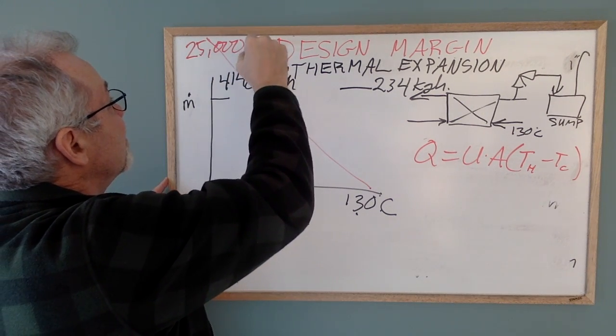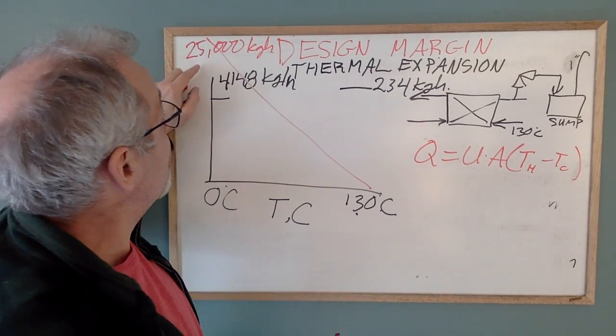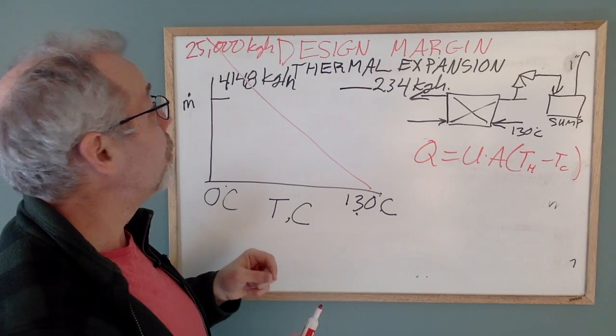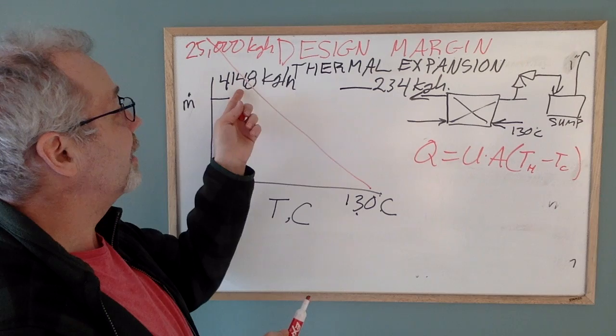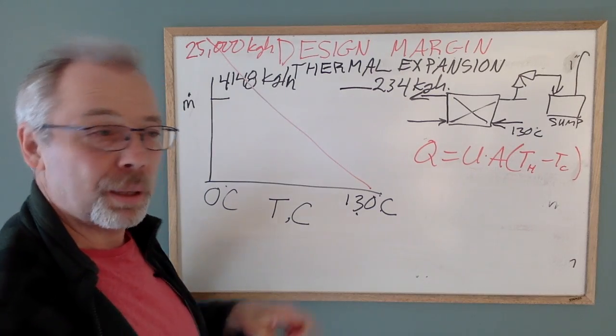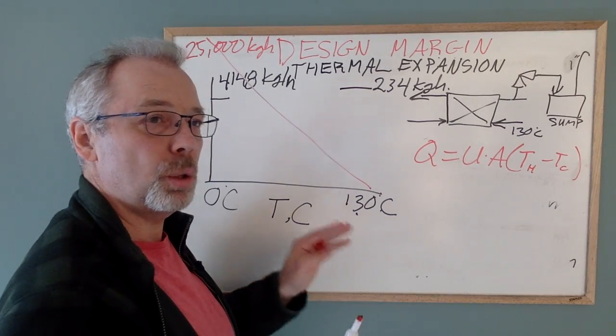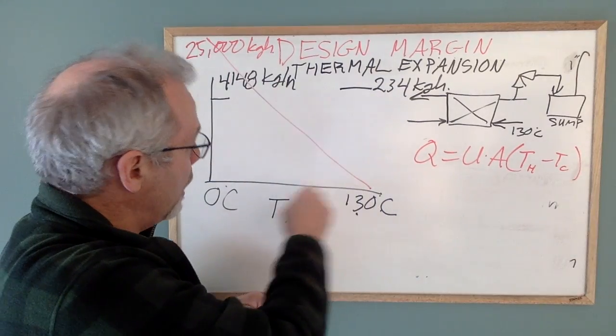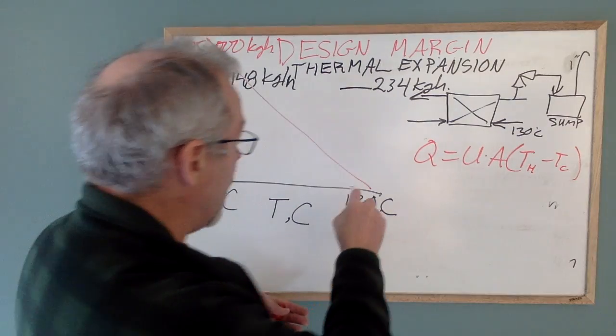The mass flow of liquid that's relieving at 0 Celsius is a horribly high value of 25,000 kilograms an hour, which causes me a bit of grief because that's vastly higher than the 4,000 and change that we got from the API calculation. But let's just put aside our urge to question the wisdom of API. Instead, let's look at the flashing steam. We'll take this flow rate and the temperature and do the flash calculation. See how much steam we make.